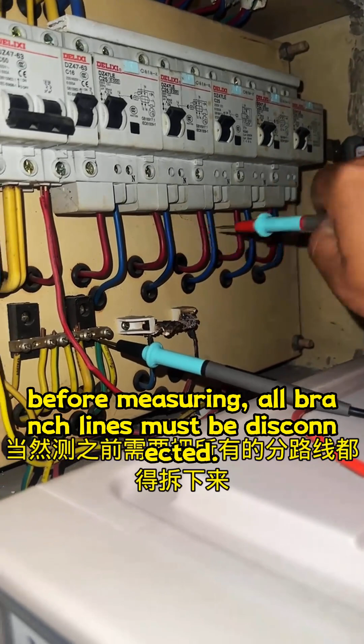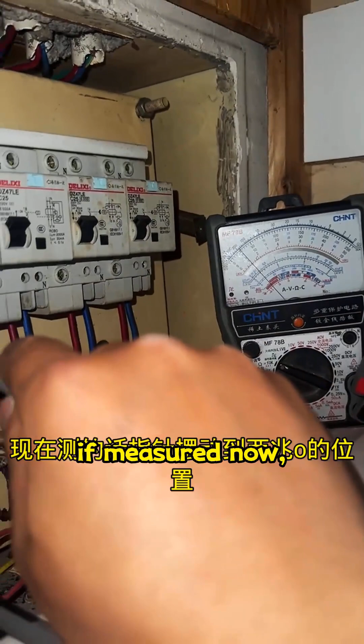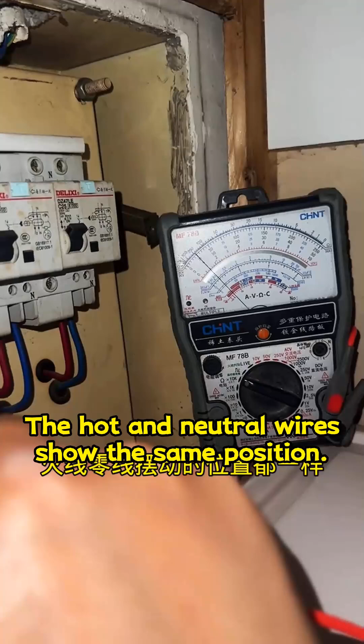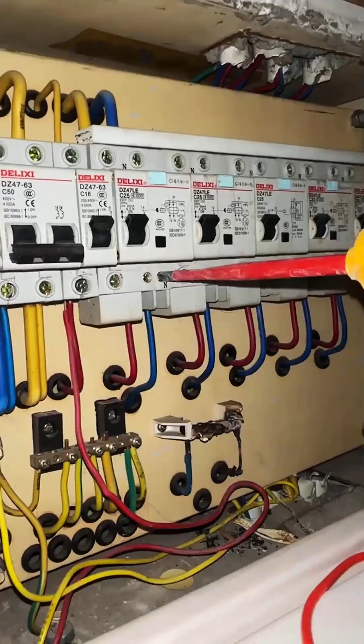Of course, before measuring, all branch lines must be disconnected. This prevents interference with measurement data. For example, on this line, if measured now, the needle swings to the 2 megohm position. The hot and neutral wires show the same position. Is this poor insulation? A test can be conducted.